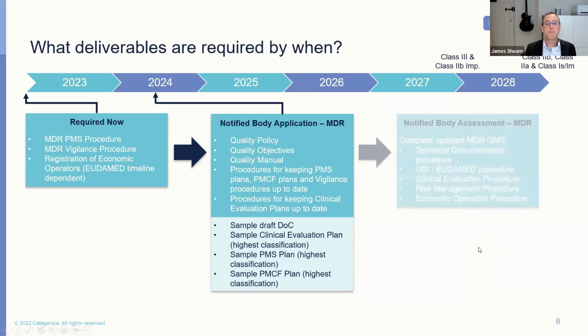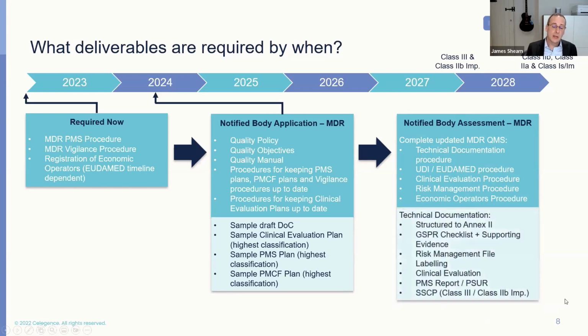And then in order to actually complete the assessment to MDR, both through a quality management system audit and then the audit of technical documentation, under the QMS, the whole transition to MDR needs to be accommodated. So that means technical documentation procedures that are compliant to MDR, along with procedures for managing UDI, EUDAMED, clinical evaluation, risk management, and economic operators. And then on the technical documentation side, at least one set of technical documentation is required, structured to Annex 2, including a GSPR checklist, all the supporting evidence for that, updated risk management file, updated labeling, the clinical evaluation, post-market surveillance report, or a PSUR, and then for the highest risk devices, a summary of safety and clinical performance. So quite a lot still to be done under there.